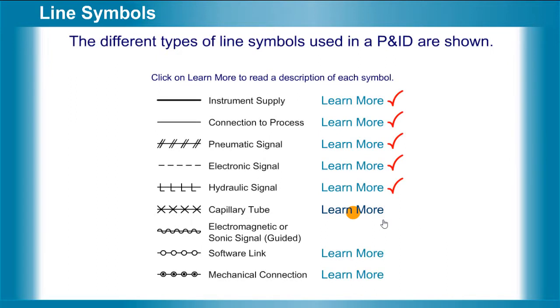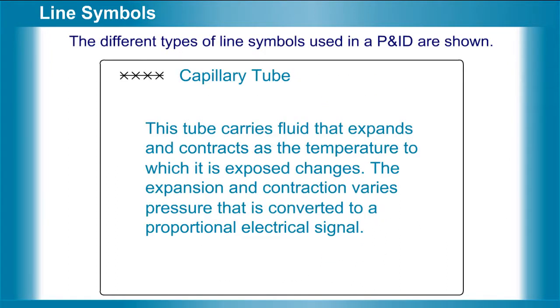Capillary tube. This tube carries fluid that expands and contracts as the temperature to which it is exposed changes. The expansion and contraction varies pressure that is converted to a proportional electrical signal.